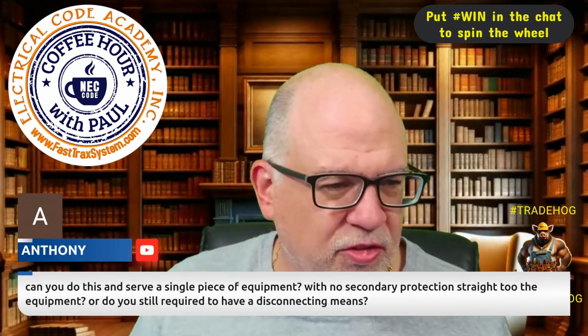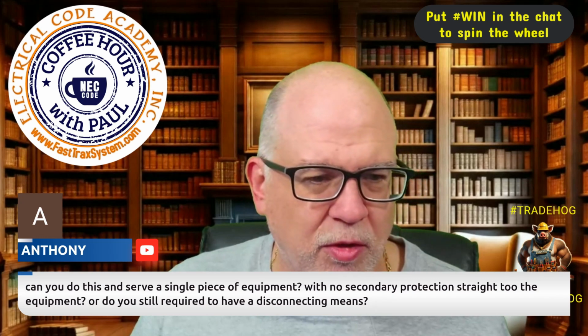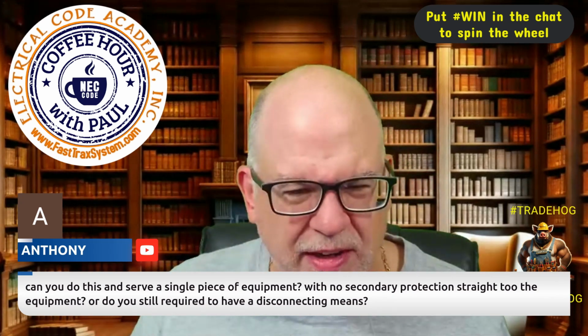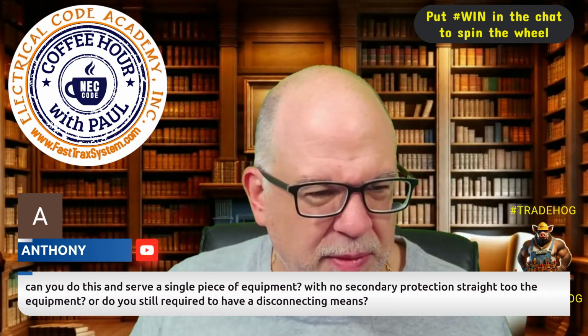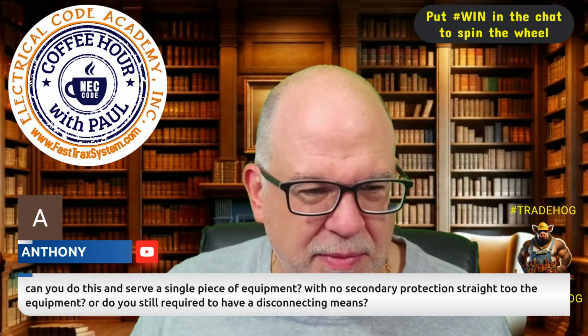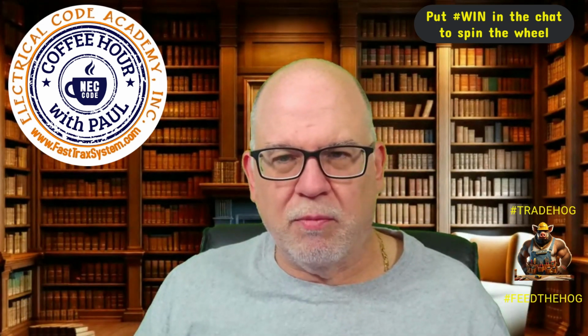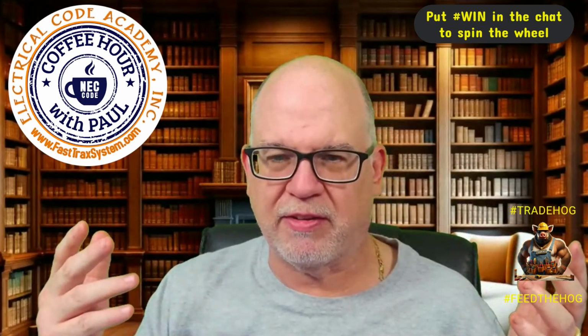And then Anthony says, can you do this and serve a single piece of equipment with no secondary protection straight to the equipment, or do you still require a disconnecting means? All over the place with the question. When we talked about the disconnecting means on the primary side, that is only if you meet the 240.21(C) requirements and you have a single voltage output. Single voltage input, single voltage output. That is when the primary protection can protect both the primary and the secondary.